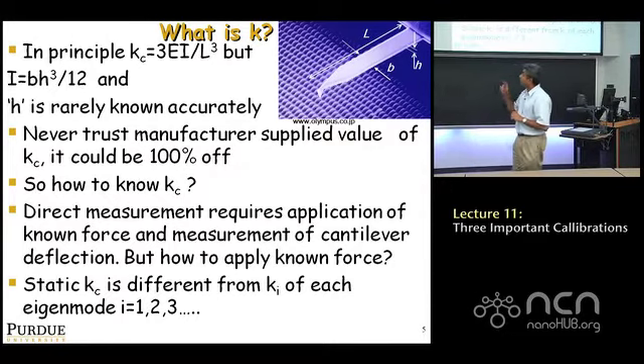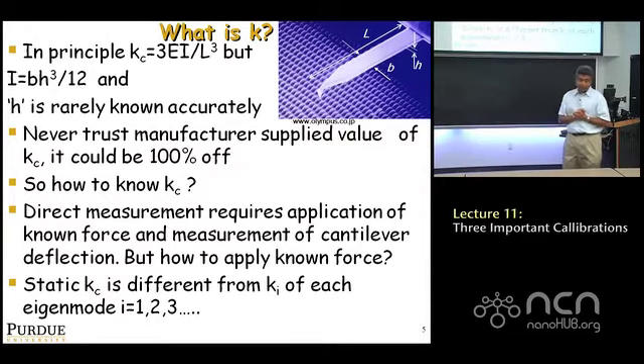And as a result, the biggest variability from cantilever to cantilever is variability in thickness, and from wafer to wafer, in fact. So even though a manufacturer tells you their cantilever is 1 Newton per meter, it'll never be 1 Newton per meter. It can be anywhere between 0.25 and 5 Newton per meter. Huge variability. You can get hundreds of percent variability in cantilever stiffness from what a manufacturer reports.